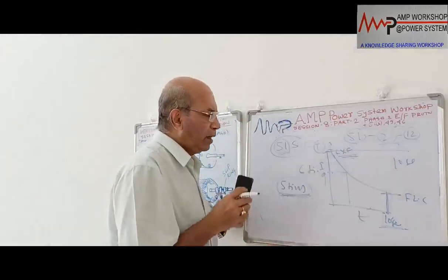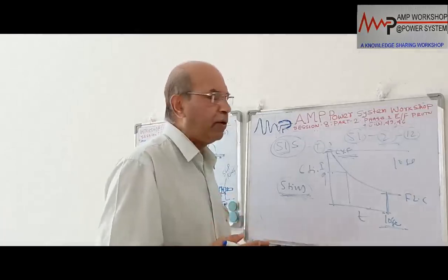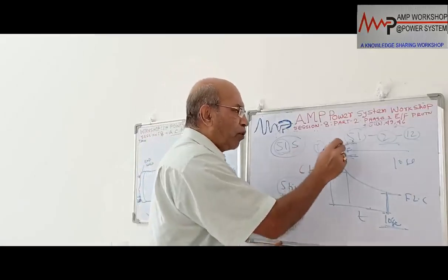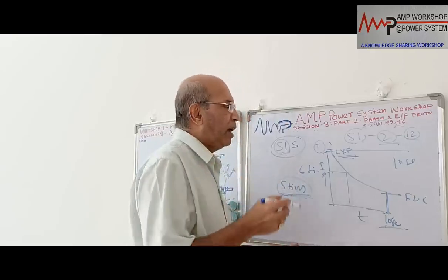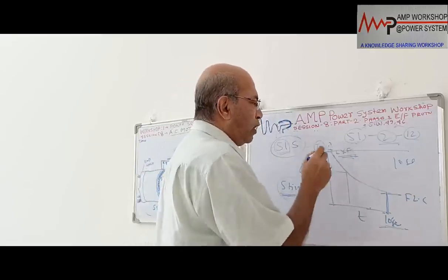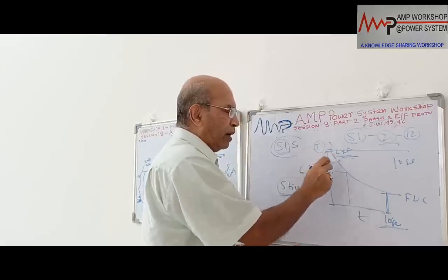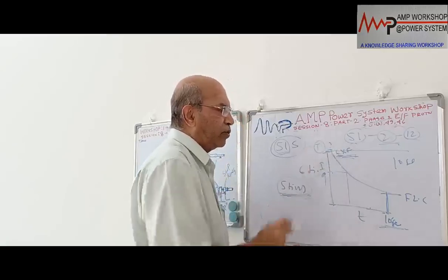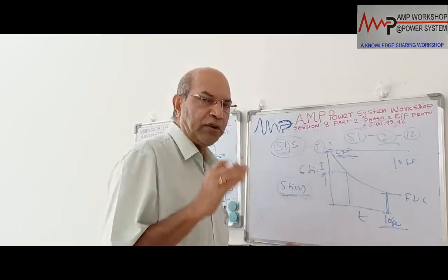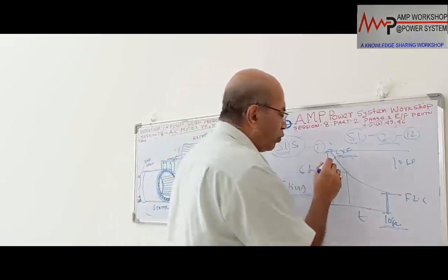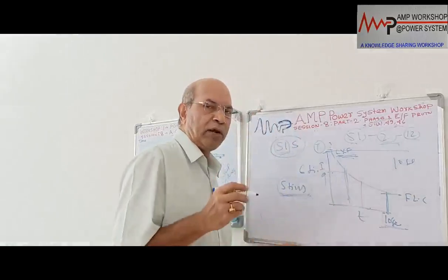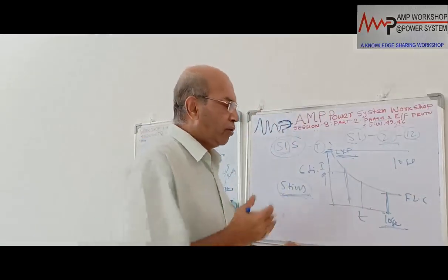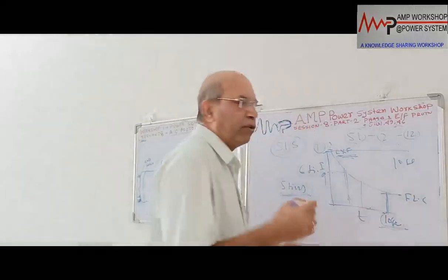And in the case of solid state relays nowadays, it's very easy. We do the programming of locked rotor. The intelligent relay can monitor the current. The moment the current picks up to the stall current, the starting current of 6 times, it will monitor and continue to monitor. If within 2 seconds the current is not dropping down, then the relay will understand it is a locked rotor condition. So it will not wait for 10 seconds. Before that it will trip.